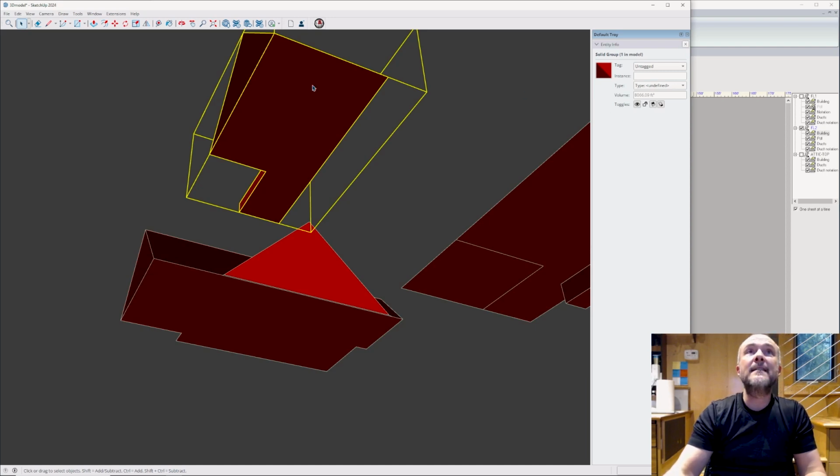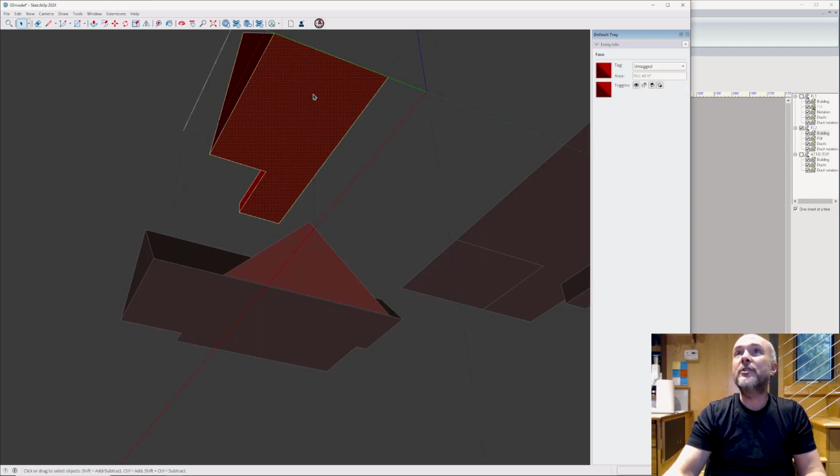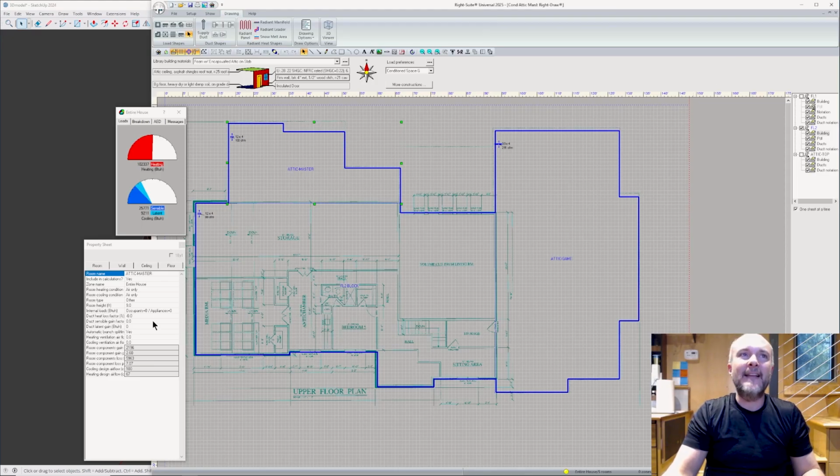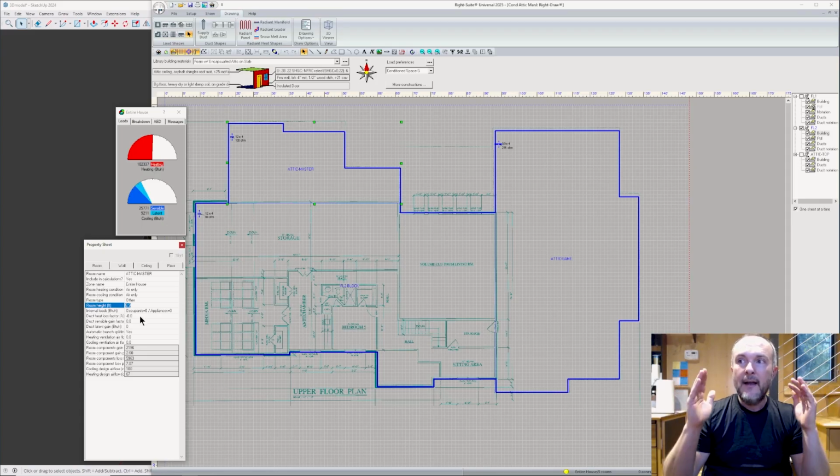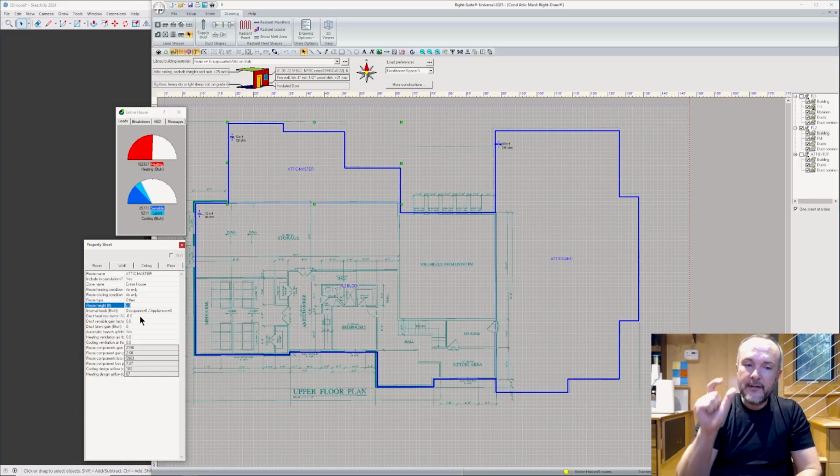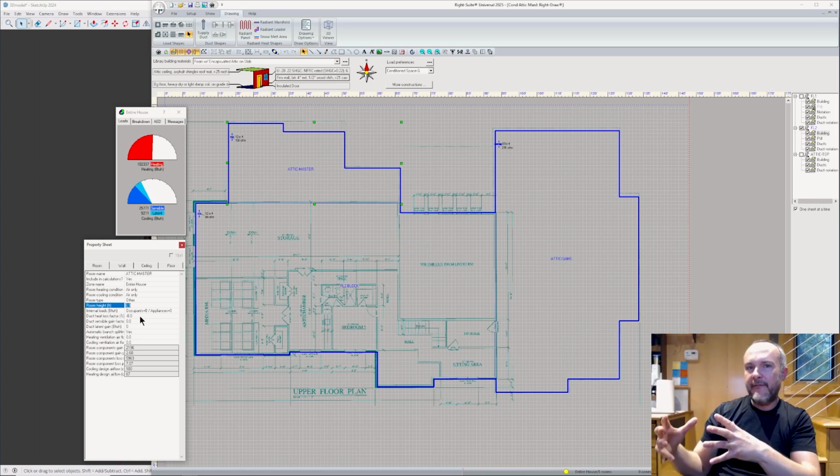I'm going to divide that by the floor area, which is 902.5 if I want to be nerdy about it. 8.9 is our ceiling height. So in this attic master, instead of 9, I'm going to make it 8.9. Am I splitting hairs? Yes, but here's the thing that happens with almost everybody else's designs when they're being floppy about it. You build fat into every single thing that goes into the software, and all that little bit of fat adds up to a giant blob of fat at the end.